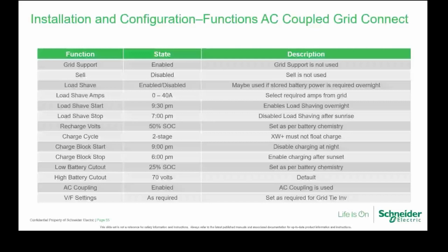Recharge volts the same as before. Charge cycle has to be two stage, but we recommend from the AC couple side, charge block, stop. Low battery cutout is basically based on the state of charge, or you use the voltage equivalent to the state of charge. High battery cutout, 70 volts, can be, depending on your settings. AC coupling has to be enabled, with voltage and frequency settings as required by the grid tied inverter manufacturer.